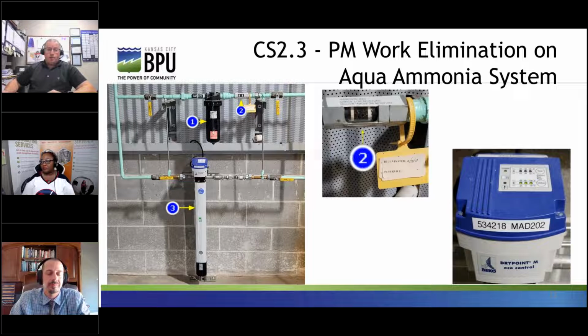I've got some items numbered that were causing a lot of PM work orders to be generated. Item number 1 is a housing for ceramic desiccant beads for taking excess moisture out of the air blanketing our aqua ammonia bulk tanks. 2 is a visual moisture indicator. The color changes from green to yellow to let us know when to dehydrate the desiccant beads contained in number 1. And an operator doing rounds daily would look at the visual indicators, and if they were yellow, they would switch to the second desiccant dryer, not shown, but previously installed where item number 3 is in the photo.